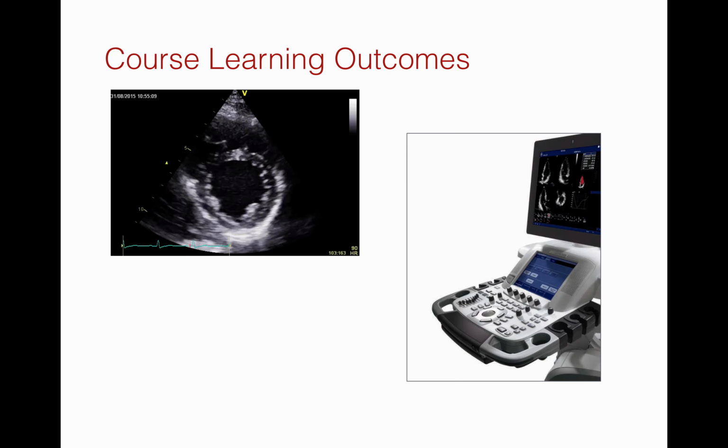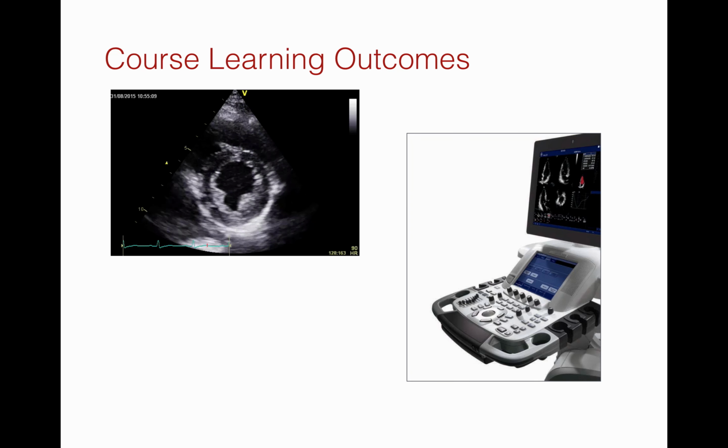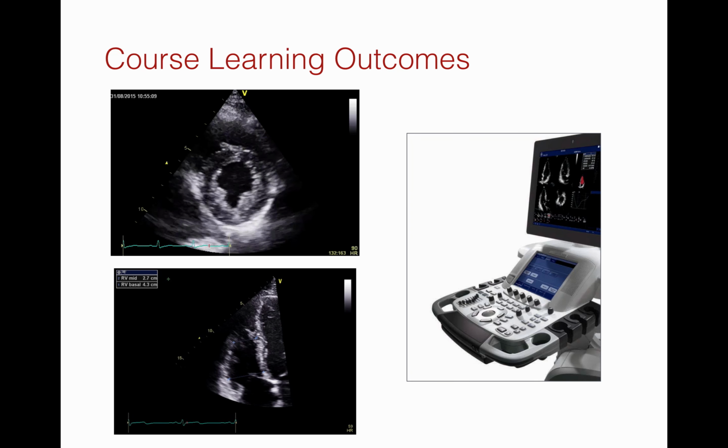By helping students recognize how to optimize images by adjusting machine settings like frequent adjustments to the overall gain and even more frequent adjustments to the time gain compensation, and by maintaining a high standard in terms of image quality and measurement technique.